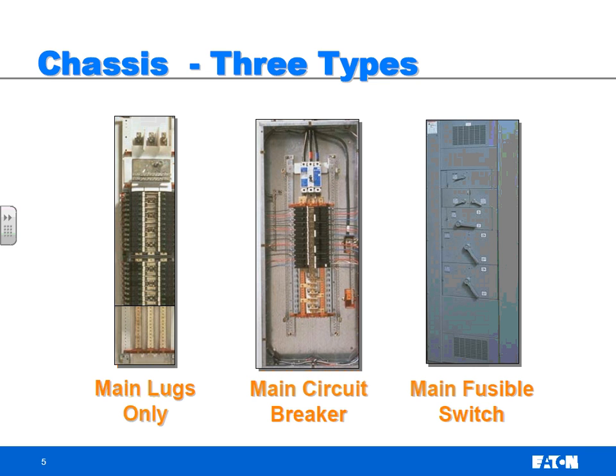Main lug is more cost-effective just because all you're doing is taking out this main breaker. Well, that has costs. Now, if you're an electrician, which do you figure you'd rather have? The guy who's actually working on it wants the main breaker, so when you walk up to the panel board, I can turn the breaker off, work on my circuitry, and when I'm done, turn the breaker on and move on. If I don't have that breaker there and I'm working on a main lug only panel, I have to go to the switchboard. Maybe that's 100 yards away or 50 yards away. I have to open that breaker, lock out, tag out, follow all the procedures, come down here, add the 120 amp circuit that I'm adding, and go back up there to re-energize this panel.